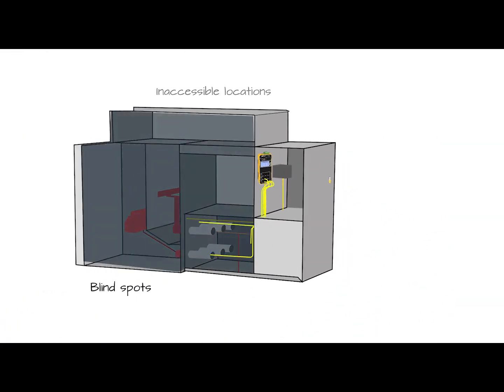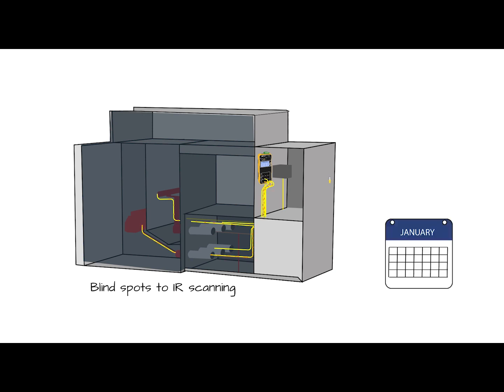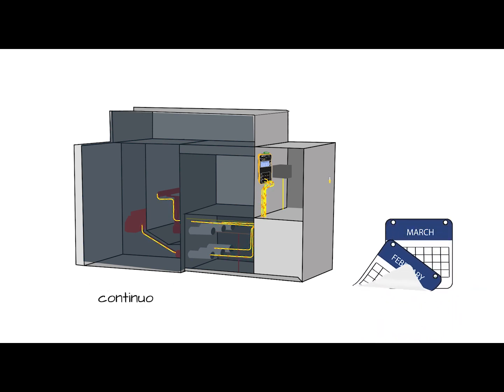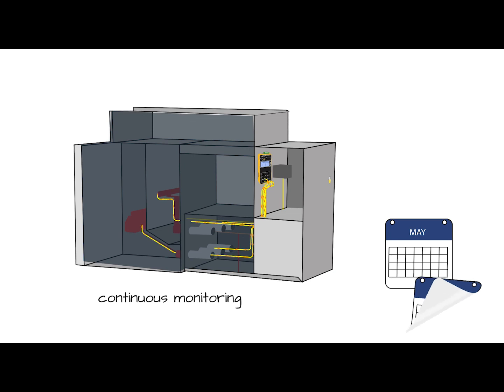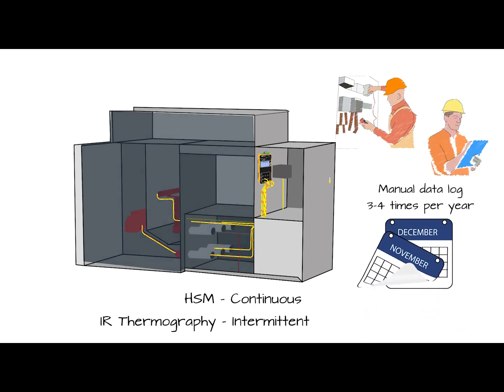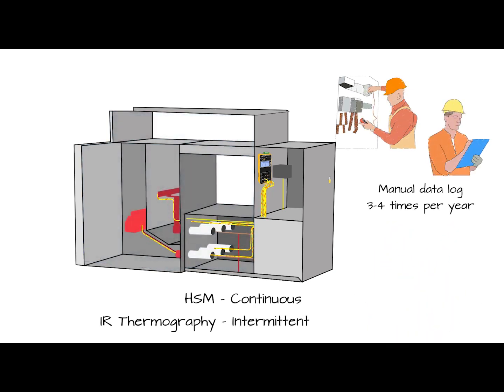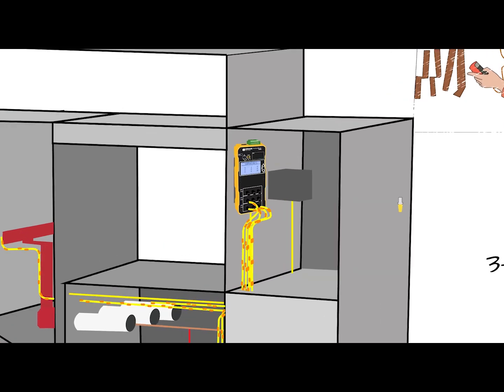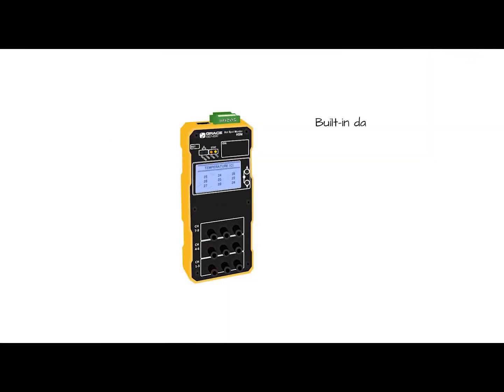Sources of heat may include inaccessible equipment and blind spots to IR scanning. The most obvious benefits of the HSM over IR thermography come from the continuous real-time monitoring feature. In addition, the successfully proven measurement accuracy of the probes is not subject to calibration errors, as can be the case with IR scans. The Hotspot Monitor comes with 16 megabytes of built-in memory for data storage.